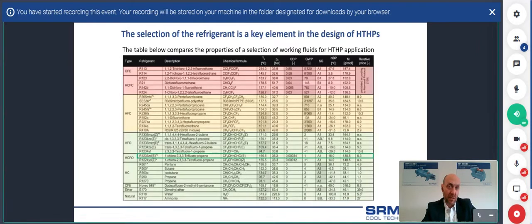We have already made the selection, and in this table we can see a list of the refrigerants suitable for heat pump operation. The red highlighted area shows the refrigerants that are already banned by the Montreal Protocol because they have a significant ODP value, so ozone depletion potential, and they can no longer be used for several years now. In the yellow highlighted area, we have the HFCs, which are the refrigerants currently used. These are also going to be banned because their global warming potential is not lower than 10. In the green highlighted area, we can see the new refrigerants that are coming onto the market and are suitable for heat pump operation.